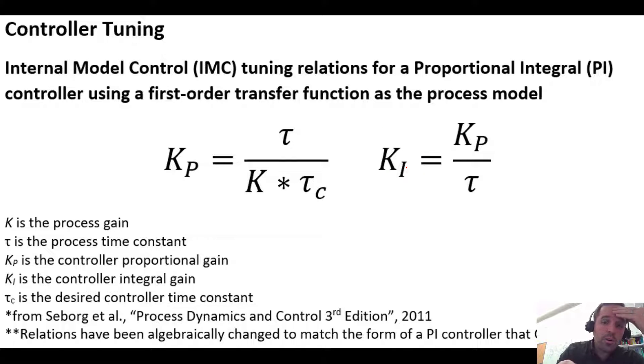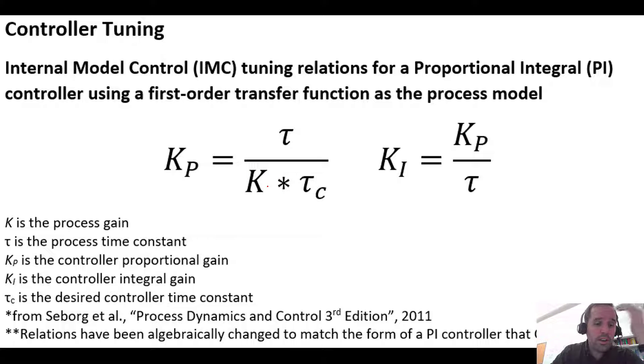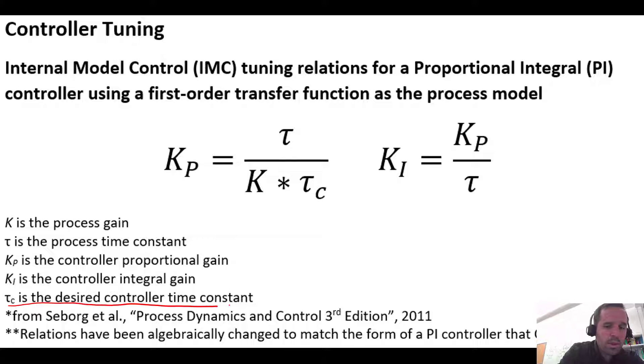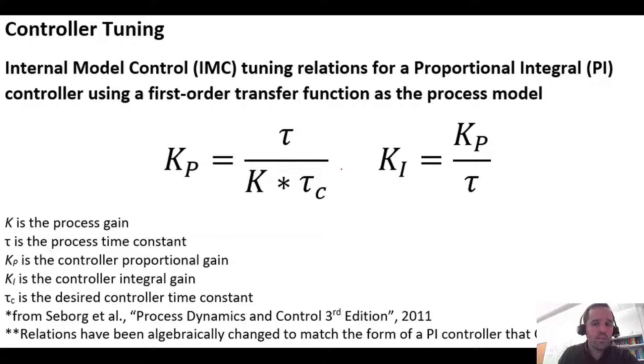To tune this, we first need to know our process parameters: the process time constant — for our valve we defined it as one minute — and the process gain, which is 0.1, with units of cubic meters per minute per valve position. Once we know these, our main design parameter is tau_c, the controller time constant. This is something we pick. Since our process has a time constant of one minute, we can make the process respond faster by setting tau_c to something like half a minute or a quarter of a minute.